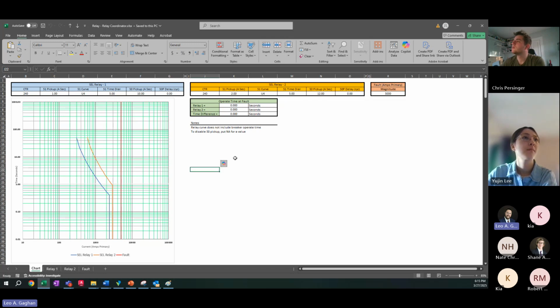So really your input data for this spreadsheet is these up here. You've got your settings for relay 1, you've got your settings for relay 2, and then you can specify a fault current. So you can see on the curve here right now, the fault current is more current than those instantaneous settings. Therefore, both relays operate without delay. We can see that right there, right? They both operate in 0 seconds, and the difference is obviously 0 seconds.